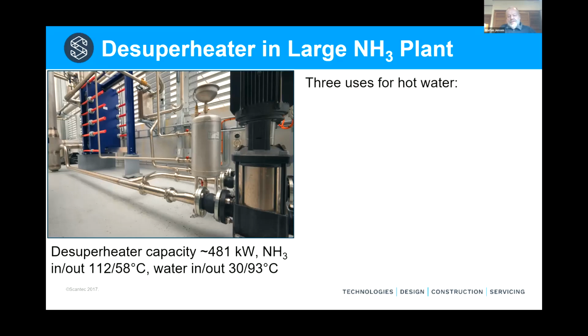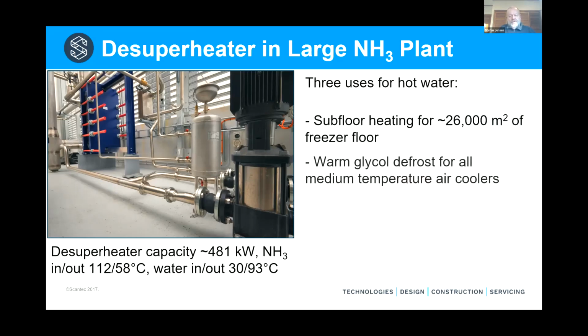In this particular case, we use the hot water for three things. We heat the subfloor below the freezer. This is a freezer floor that's about 240 by 120, 110 metres in that order, 26,000 square metres. So the design capacity is about 16 watts per square metre, but that's not what the floor uses. When the freezer runs at about -20, it uses between 1 and 2 watts per square metre, but we design for 16 for a number of reasons that I won't get into here.